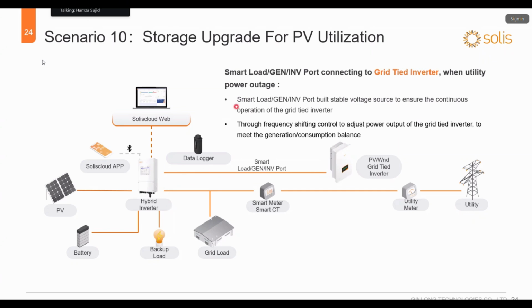Okay, so actually the smart port load will provide the stable voltages to the source to ensure the continuous operation of the grid tied inverter. Through the frequency shifting control, it adjusts the power output from the grid tied inverter to meet the generation and consumption balance. So how the inverter is going to control the output of the inverter is through this frequency control or frequency shifting control.